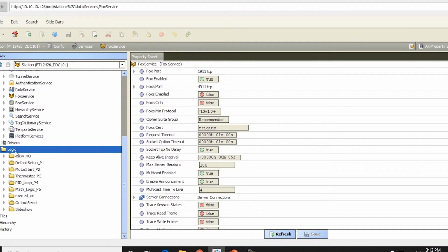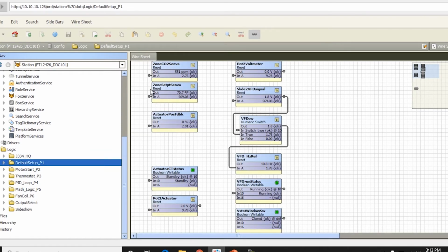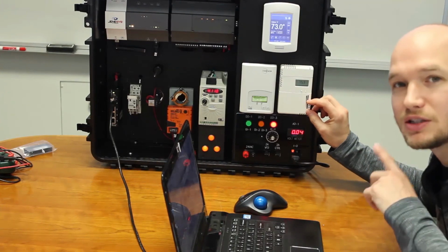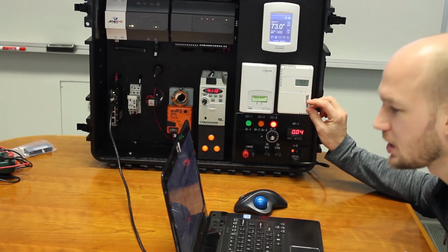So in the logic folder here, this is where most of the application operations are carried out. So you can see the different subfolders, right? If we go into default setup, here's our wire sheet we talked about. And so if you're looking at here, you can see the output. This will feed into the input. That's true. There's an output here, it feeds into the VFD hertz. So as I move this sensor up and down, it's going to change on the wire sheet.